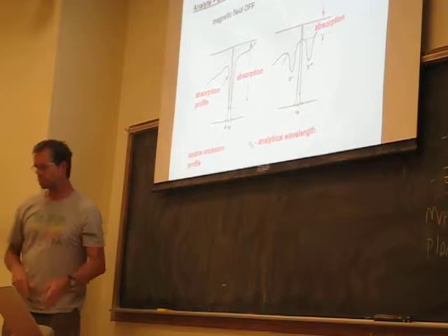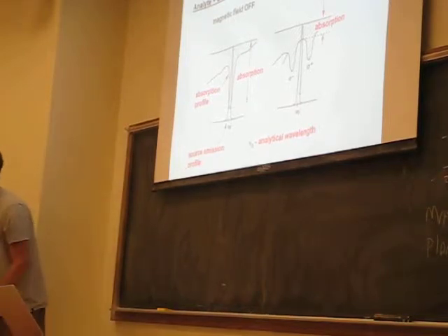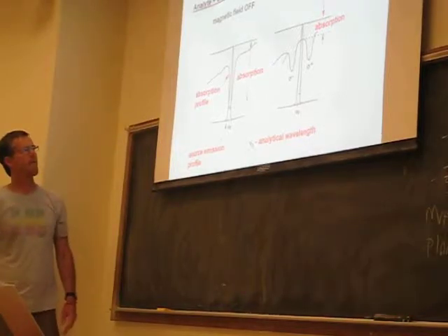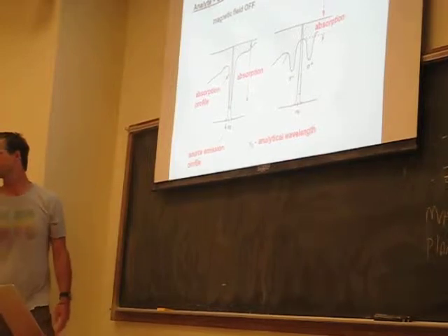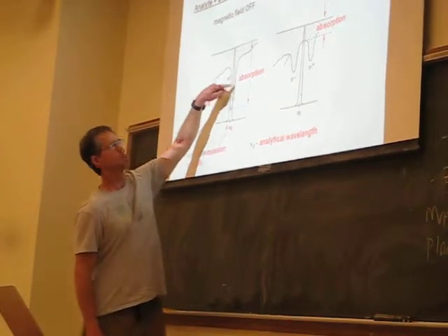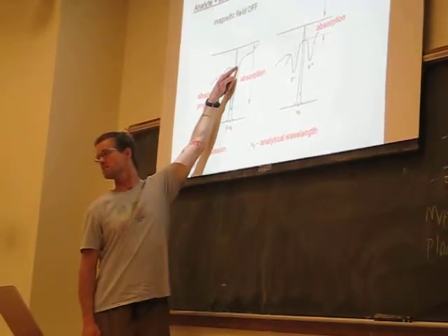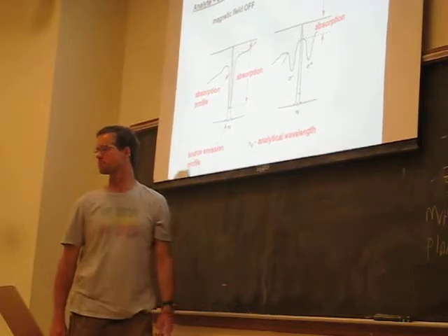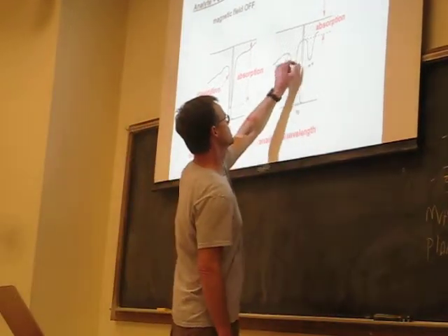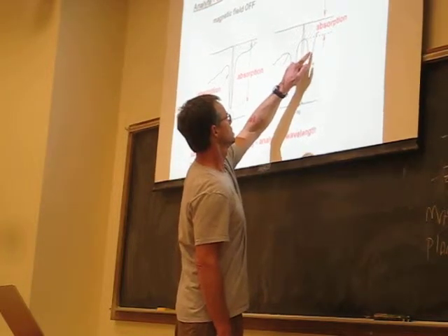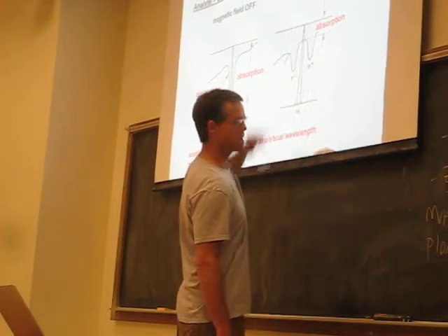The sigma absorption profile is the magnetic field off. Sorry, say it again. Are the sigma absorption profiles present in the magnetic field off? No. They're off, because when it's off, you just get this one absorption line, right? And it's in the presence of it being on that the atomic absorption line is split. And that's what allows us to use the magnet on to distinguish, not measure what's atomic, but measure the non-atomic absorption profile.